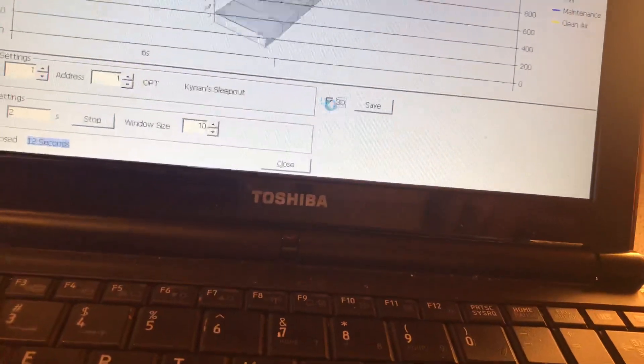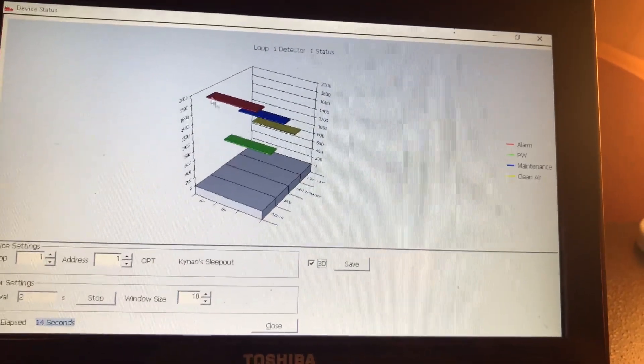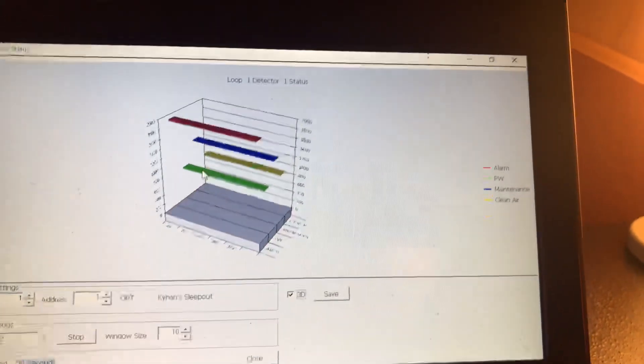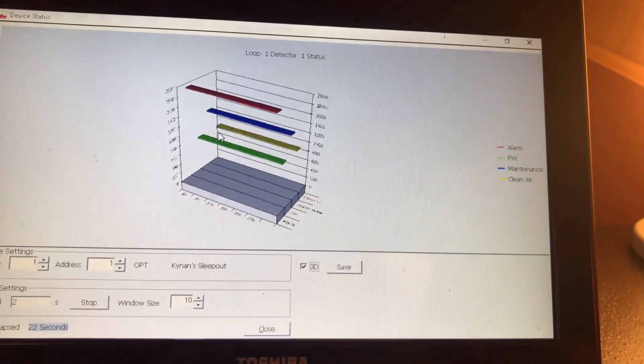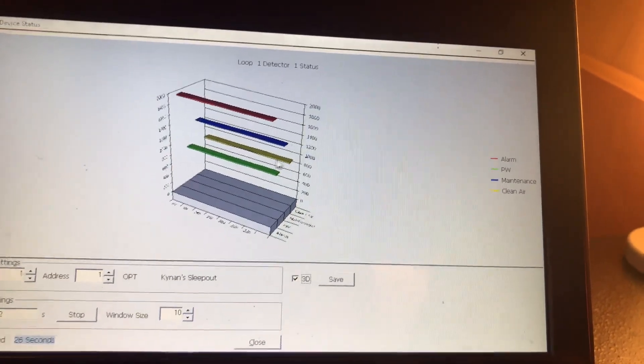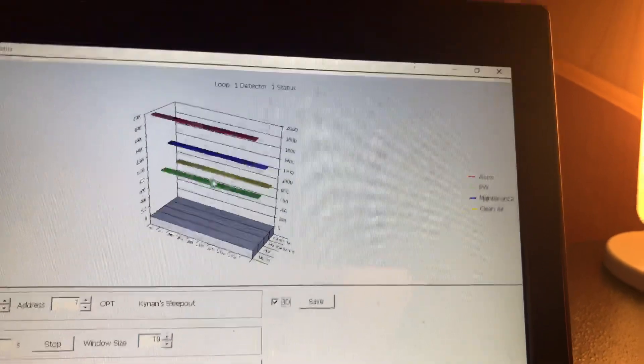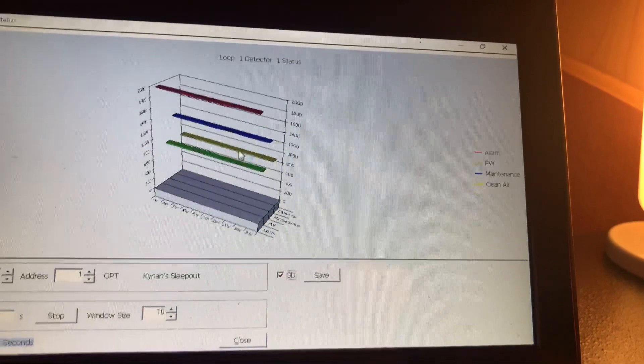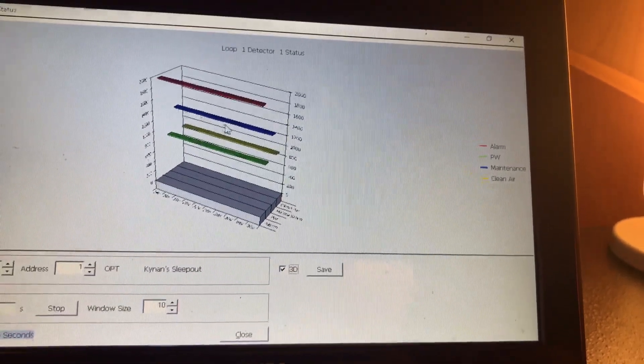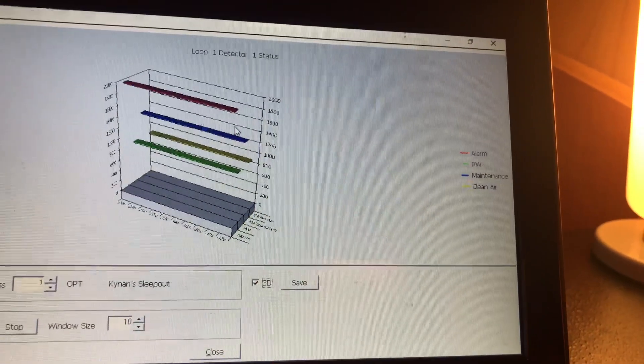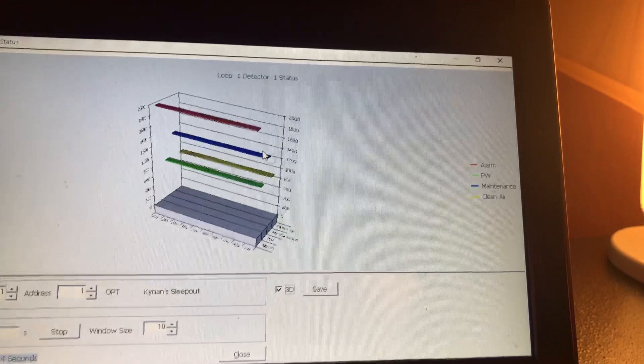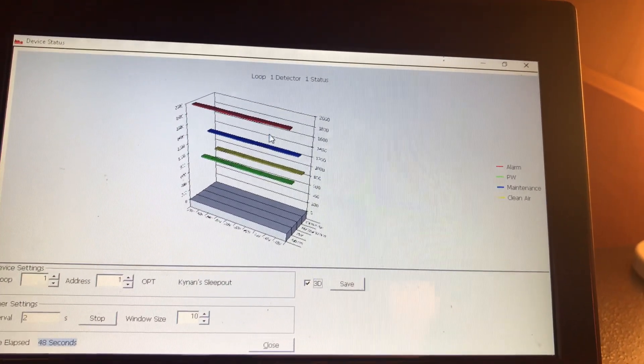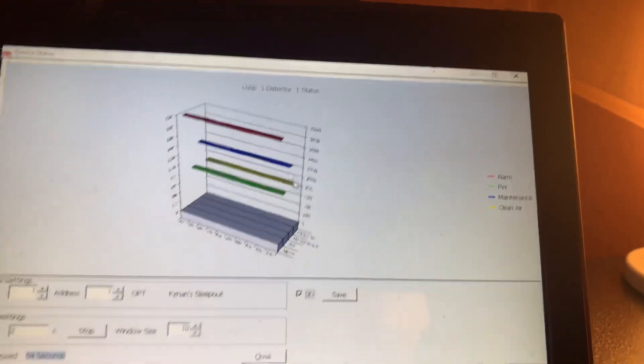You can see a live view of the smoke alarm status, so how much smoke is in the chamber essentially. It'll take a while for it to load up here. We'll go into a 3D view for added effect and you can see the green bar here is your PW value. So that's the value that the smoke alarm is outputting. This is a fresh air value, so this is what the detector should be showing. You can see I keep my detectors very clean. So the actual smoke detector value is below the normal value. This blue value here is maintenance. So if your smoke alarm is above this blue line, you need to clean it. So this is a really great tool for figuring out which detectors are dirty and need cleaning. This red bar at the top should be pretty self-explanatory. This is the alarm value.